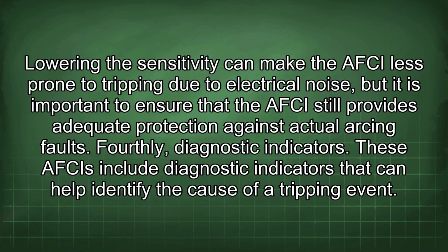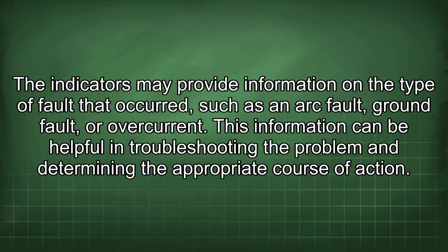Fourthly, diagnostic indicators. These AFCIs include diagnostic indicators that can help identify the cause of a tripping event. The indicators may provide information on the type of fault that occurred, such as an arc fault, ground fault, or overcurrent. This information can be helpful in troubleshooting the problem and determining the appropriate course of action.